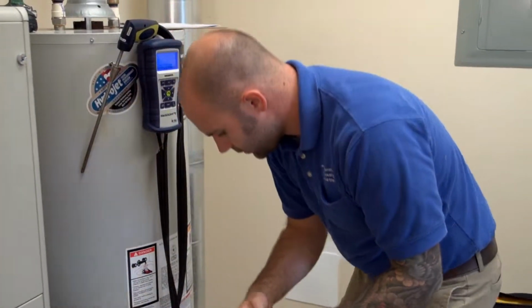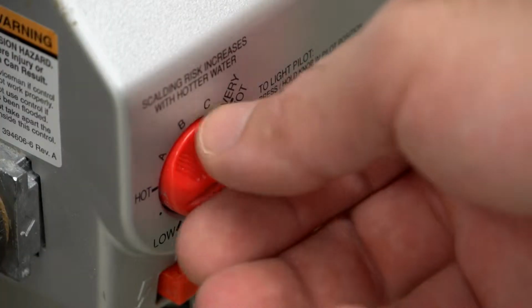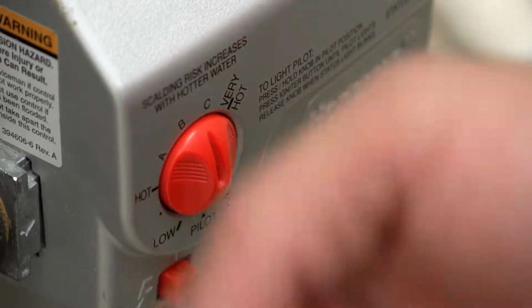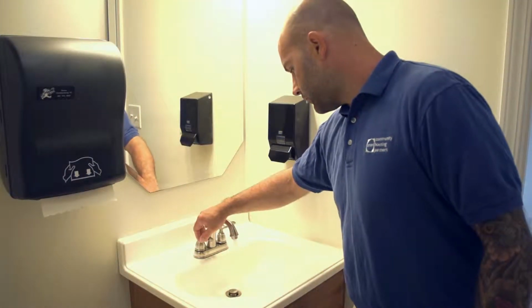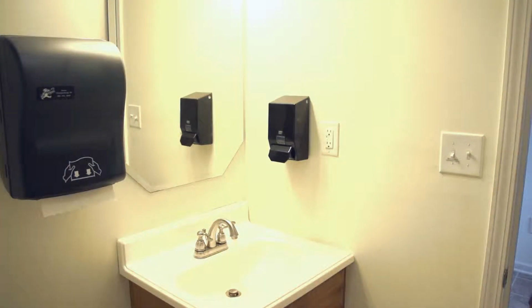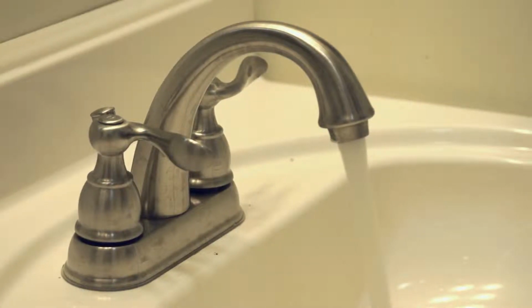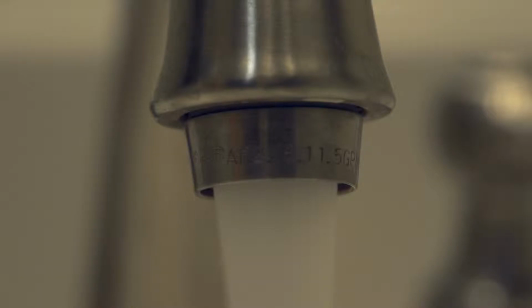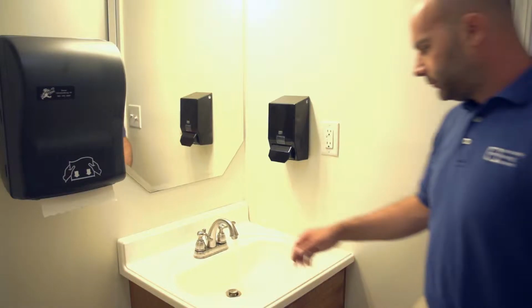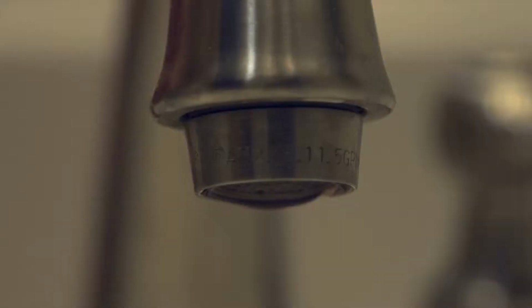Next, fire the appliance. You can fire the appliance one of two ways. Simply turn up the temperature on the tank, taking note of the current setting, or turn on the hot water at a sink or bathtub. Choose a fixture that will keep the appliance on for at least 10 minutes. Sometimes the sink may not have enough flow to do this. If you choose to turn the temperature up to engage the firing process, it is important to dump the superheated water after the test to ensure no one is scalded due to the temperature increase. It might be a good idea to mention this to the client as well.